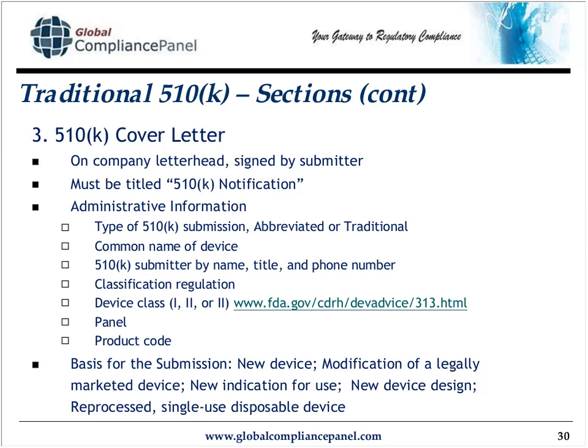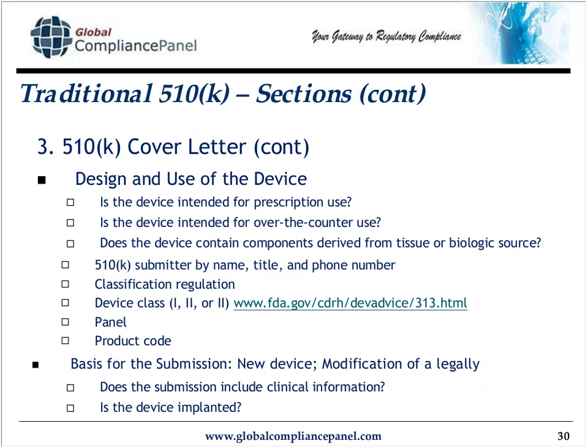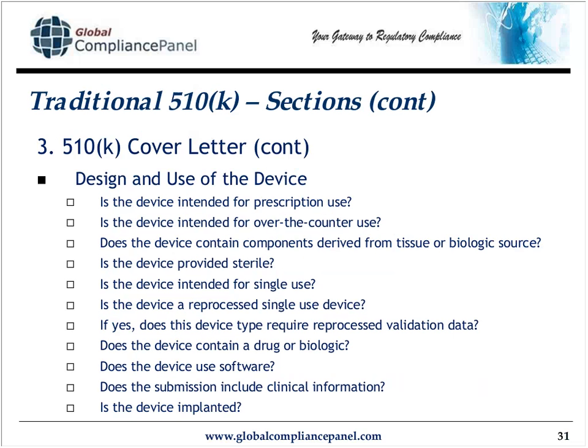And why am I submitting this document? Is it new? Am I modifying it? New indication for use? Just something to give the reviewer a heads up as far as what to keep an eye out for. The next section of the cover letter is the design and use of device, and I've got to answer each of these questions. I'll just pretty much copy, paste, and write yes or no after each of these.